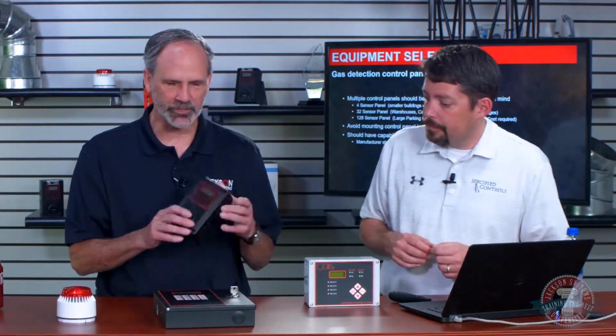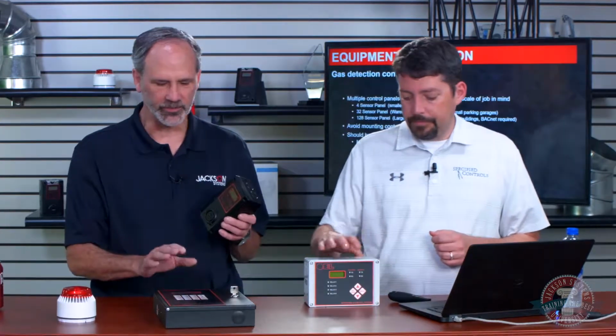Yeah, we'd normally put the address of the sensor, so when the main panel says sensor 3 is in alarm, you know right where to go to look. The panel's pre-programmed for you. You can program it yourself. It comes with software, a little software CD and a USB serial cable. Real easy to program on your own as long as you carry a laptop. I personally don't even want to do it through the front panel. The software documents everything that you did, which is really, really important to us.